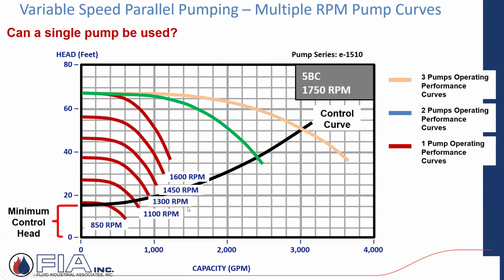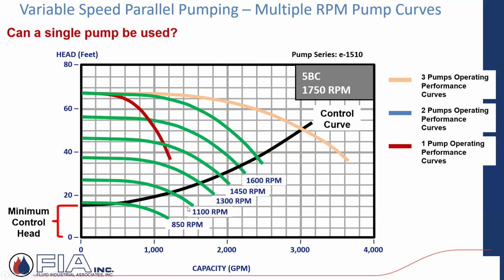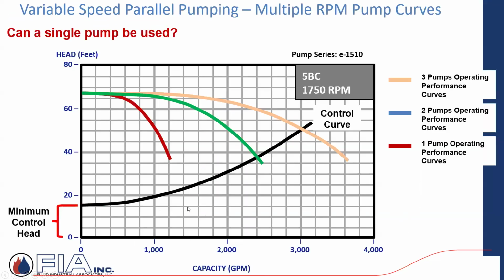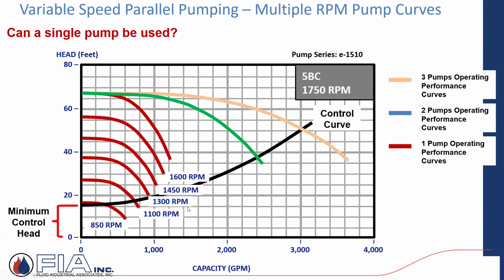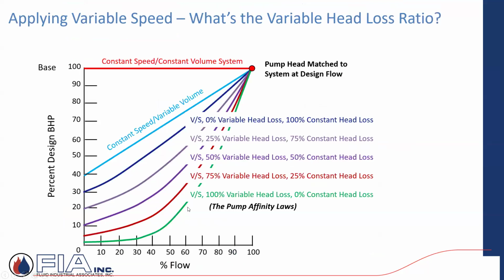And then the final question and example would be, if a single pump was running, could that single pump still achieve certain conditions within that system? And the answer is yes. That curve at 1100 RPMs is still intersecting that system curve, or that really you'd call it that control curve. So it's down near the end, but I could really run about 25% or 750 gallons a minute. So that's not uncommon to do parallel variable speed pumping. When I need it all, I'm out here at that 3,000 gallons a minute. And then as the load changes and valves are closing and I can start backing off pumps, I can do that. That's a common application for variable speed.